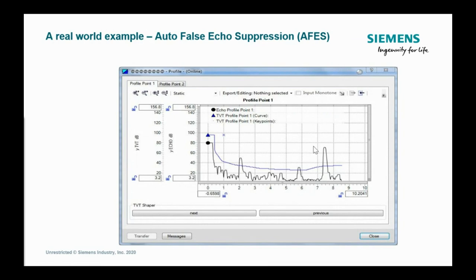And it would stay locked onto that high level until either the process improved and we got a strong enough echo off of the material, or if they cycled power. When you cycle power, you kind of reset that filter and it would take a fresh look at it, and it would go, oh, okay, there's my echo down there. So I went, perfect. I know exactly what we're going to do, and we did something that's called auto false echo suppression.